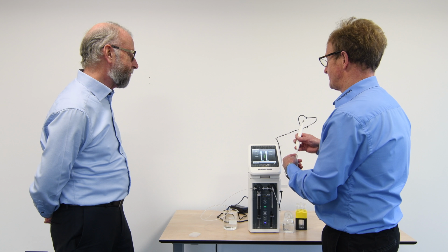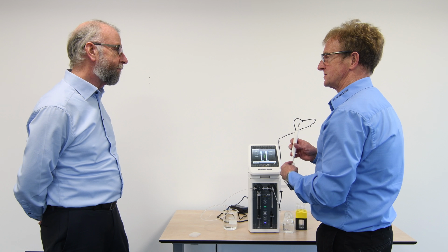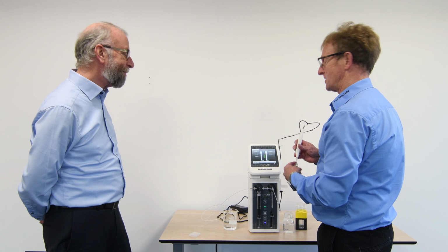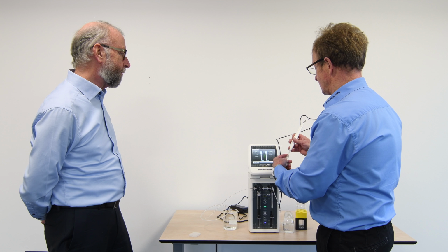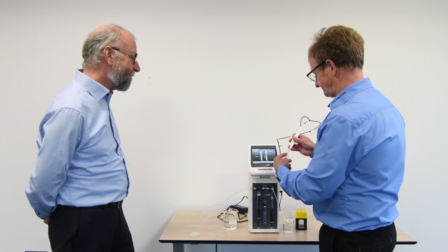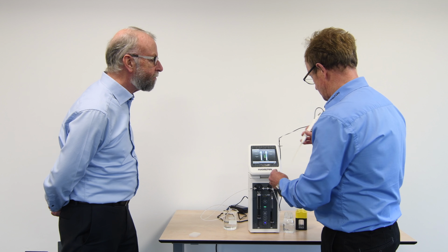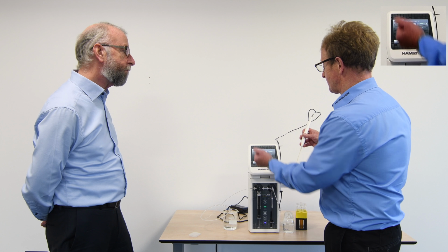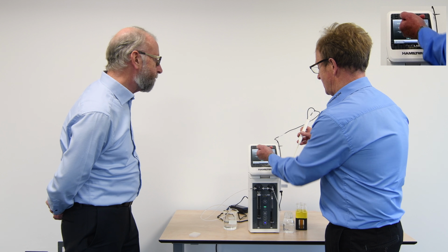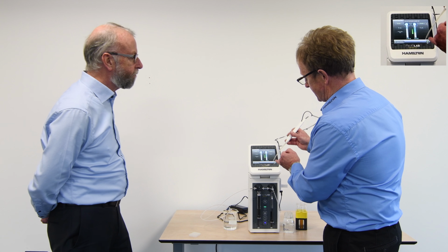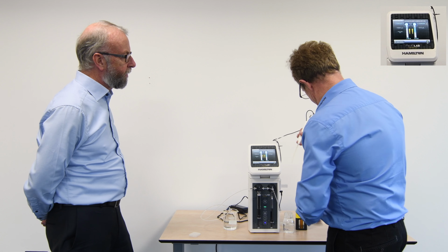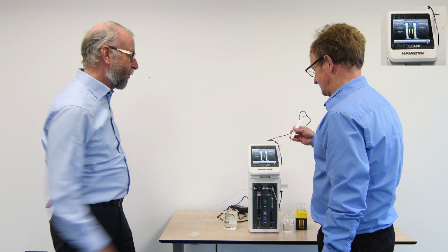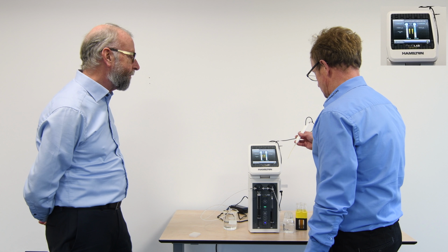Exactly. If the technician gets disturbed or has any other issues going on, it tells them immediately the stage they were at. So here we're aspirating our sample. Yeah, good. And we've picked up sample as per the previous step. And you remember what the next step was, pick our air gap, and we can say pick up air gap and wipe tip. So I can do just that. I can pick up a small air gap. So you wouldn't accidentally have the tip in liquid. Exactly. At that step with this text here. Okay. That's exactly the point.